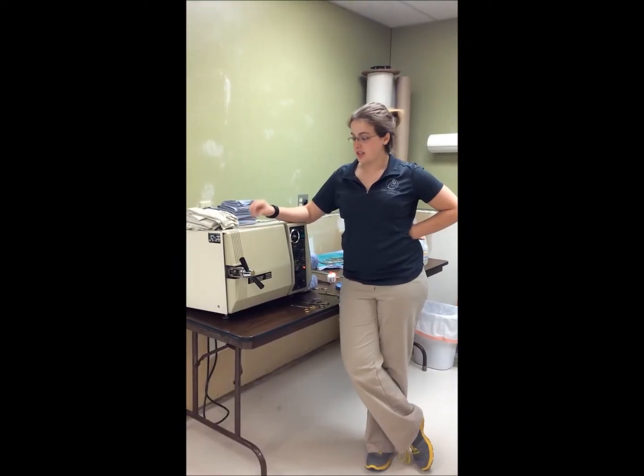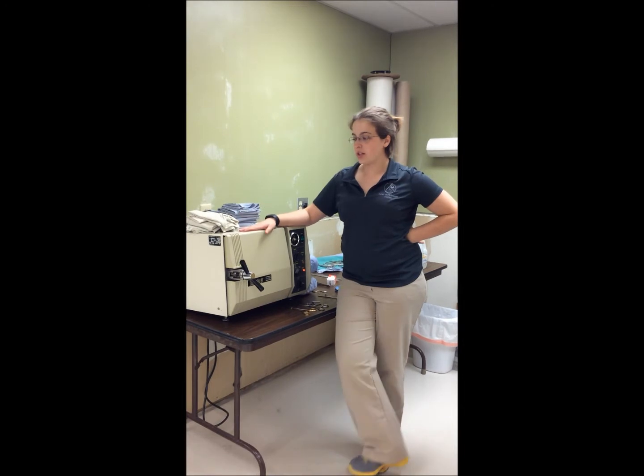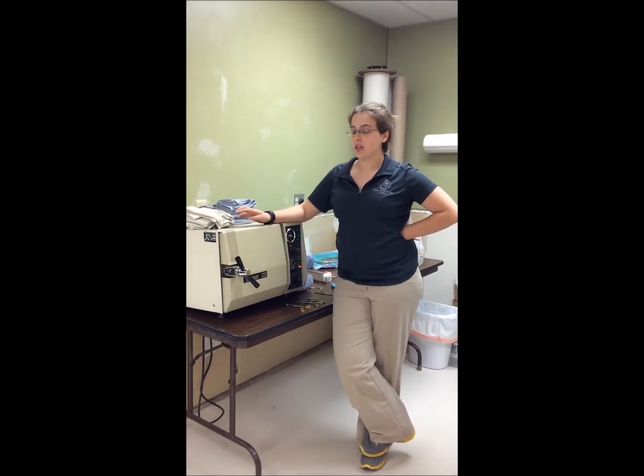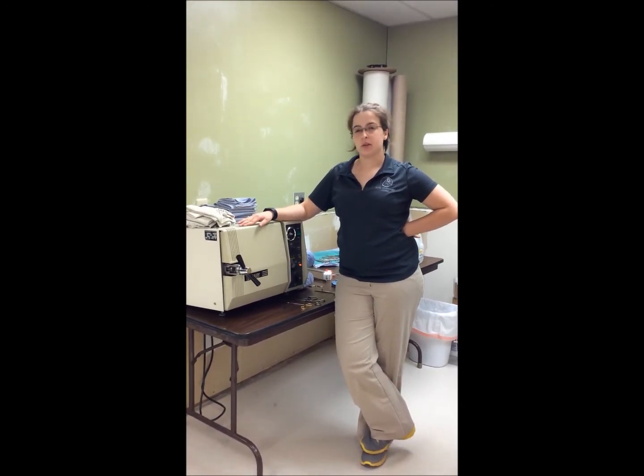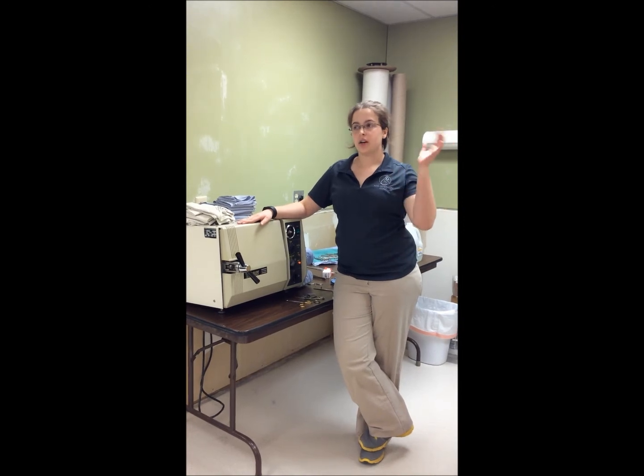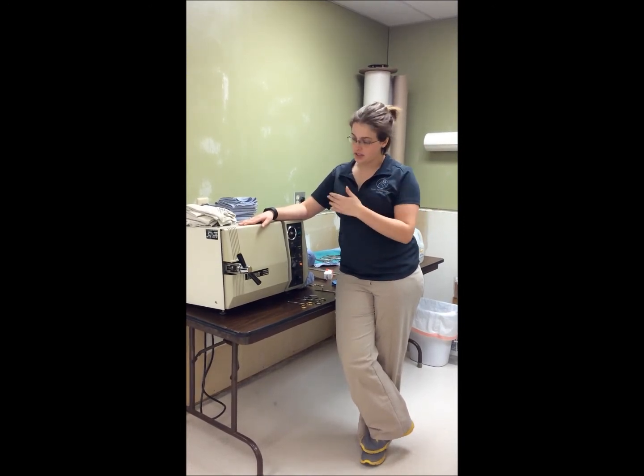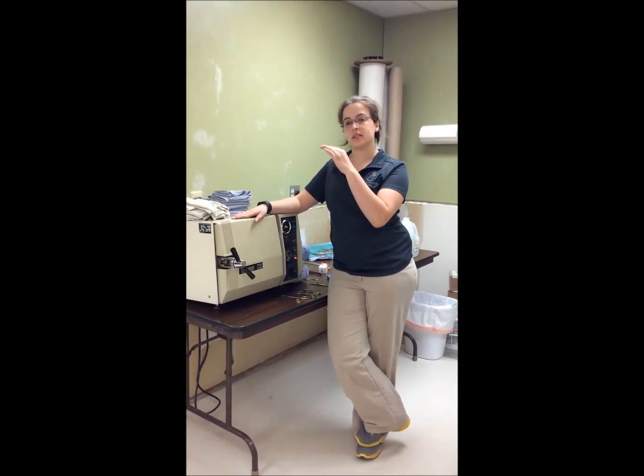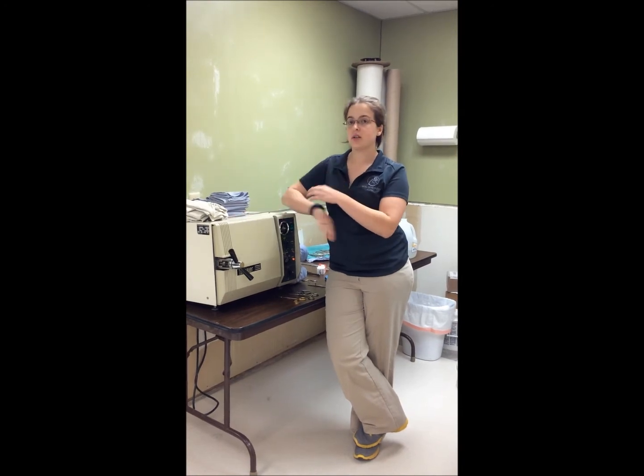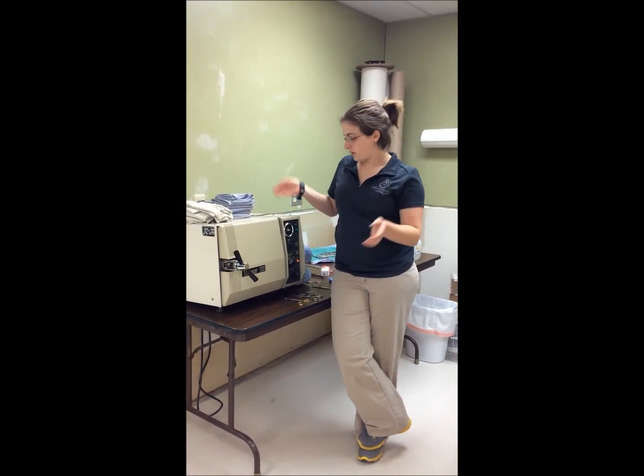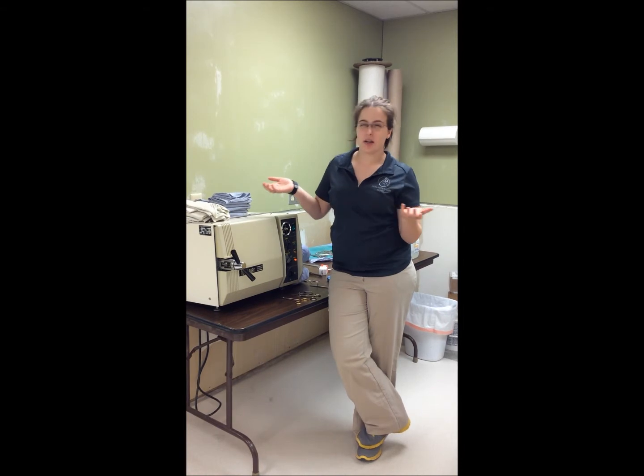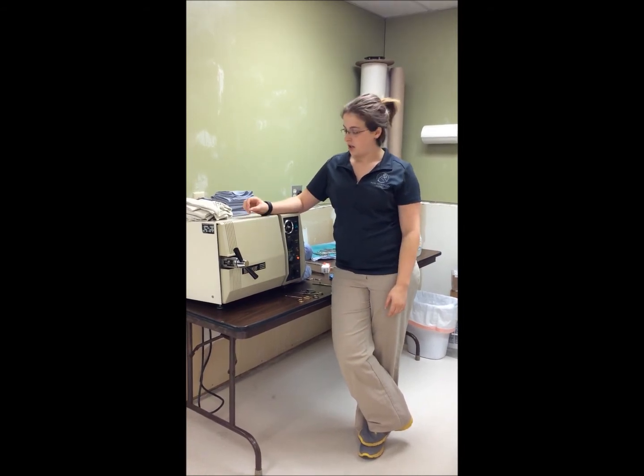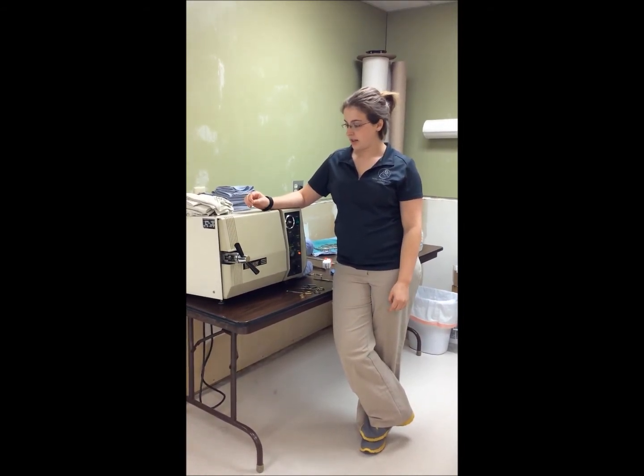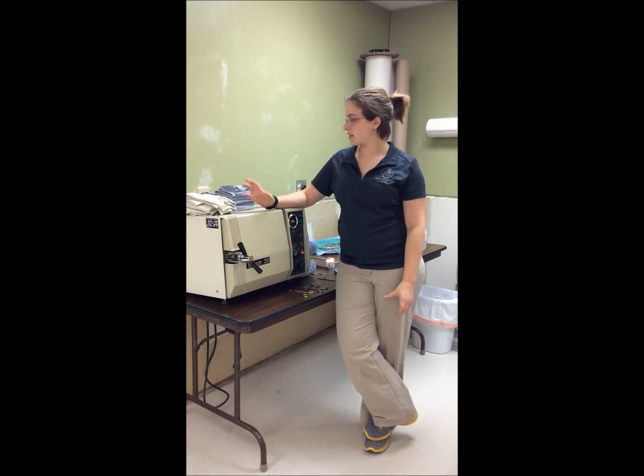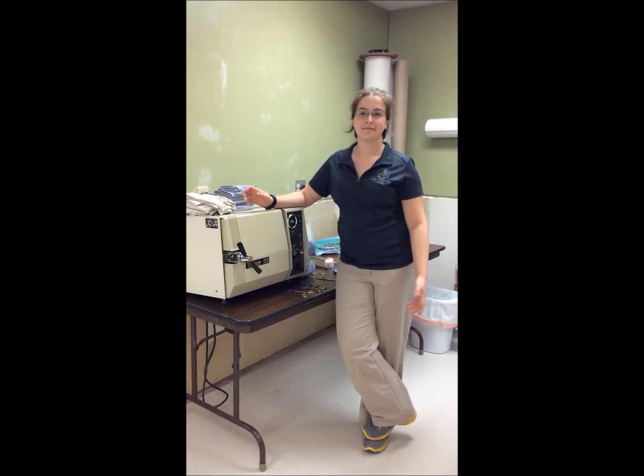Okay, so this is our autoclave, and we get it serviced once a year, and then we have it cleaned out about once a month, where we'll drain all of the water out. We'll clean the inside, and then we have a rack that the packs sit on that we'll clean as well. And then we'll refill it with fresh water. We do that all about once a month. And that's kind of what our manufacturer recommends.